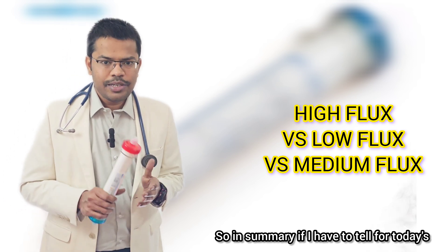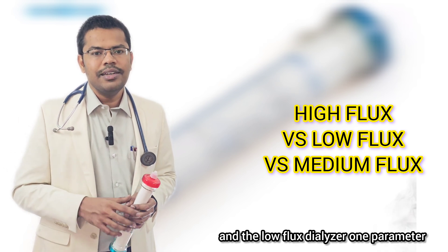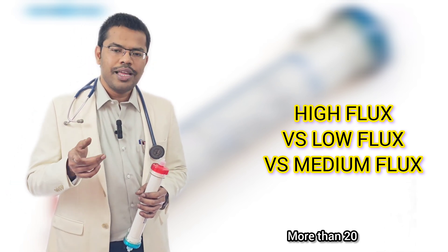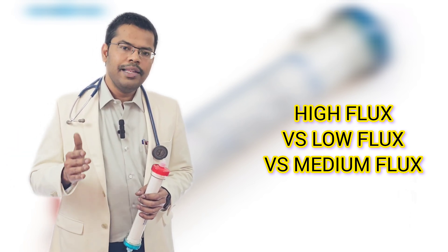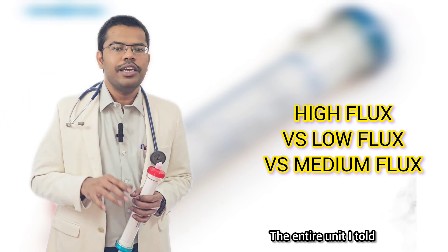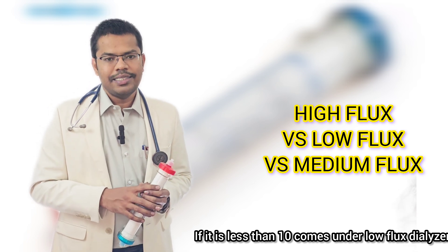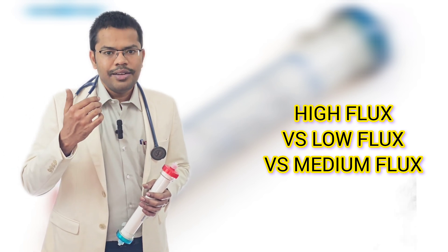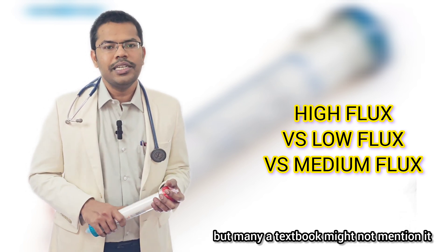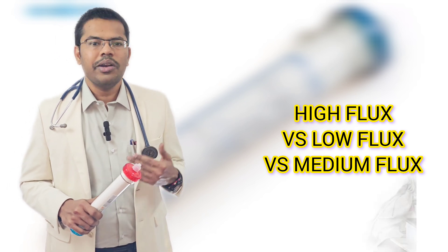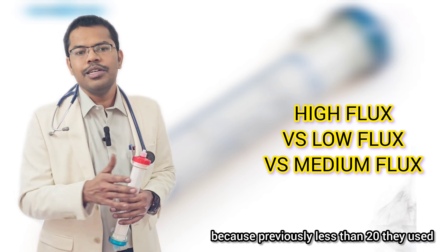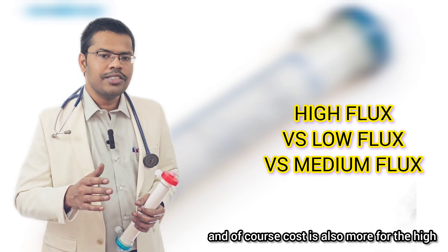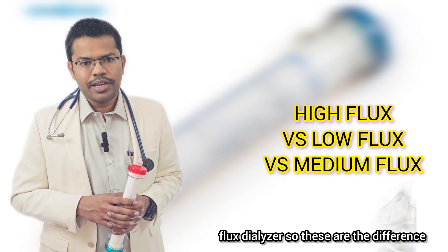In summary for today's episode on high flux, medium flux, and low flux dialyzers: the predominant deciding parameter is pore size, technically expressed as KUF or ultrafiltration coefficient. KUF more than 20 ml per millimeter of mercury per hour is high flux; less than 10 ml per millimeter of mercury per hour is low flux; between 10 and 20 is technically medium flux, though many textbooks may not mention this term. Molecular weight clearance and cost are both higher for high flux dialyzers.